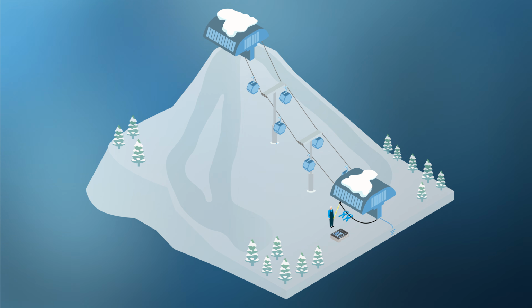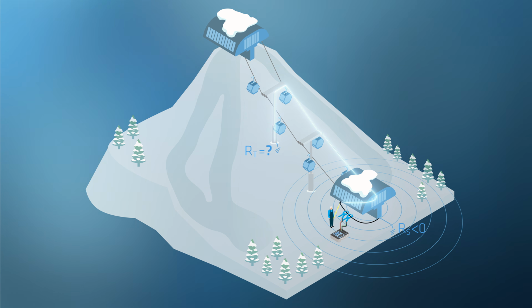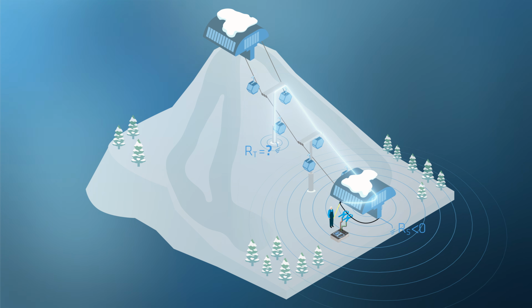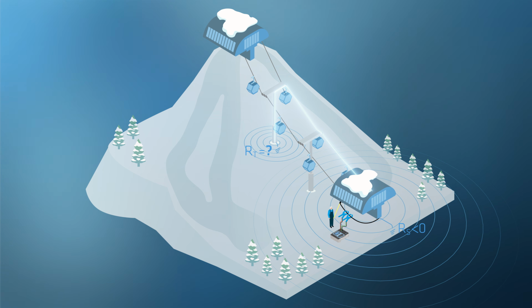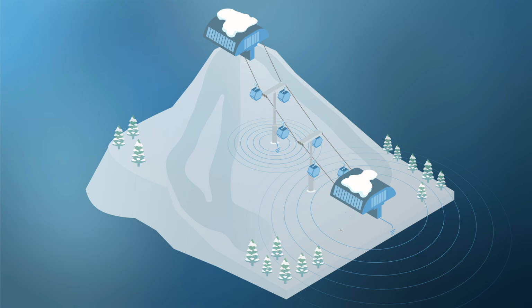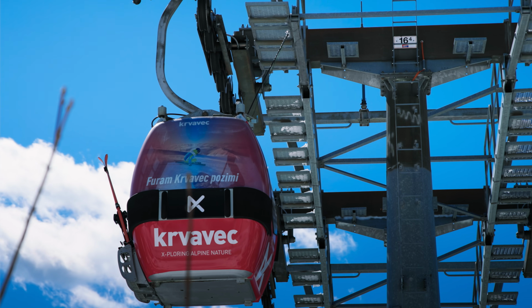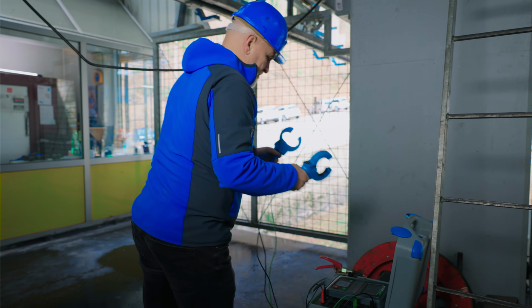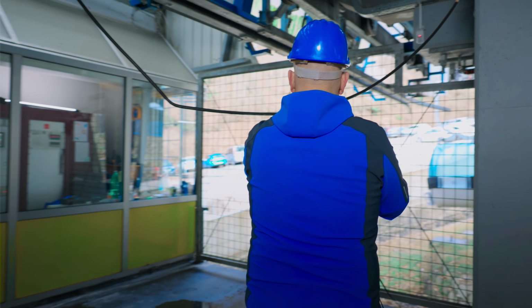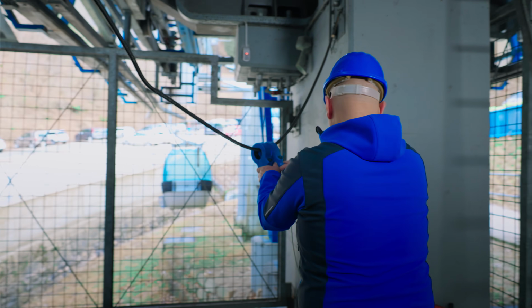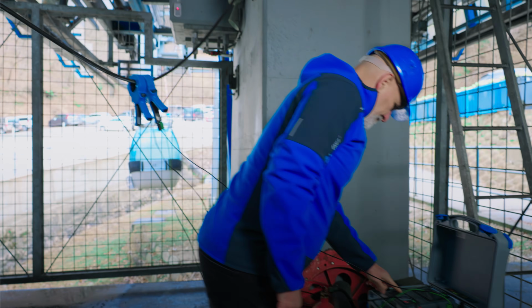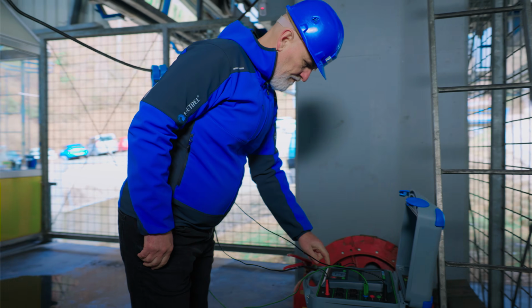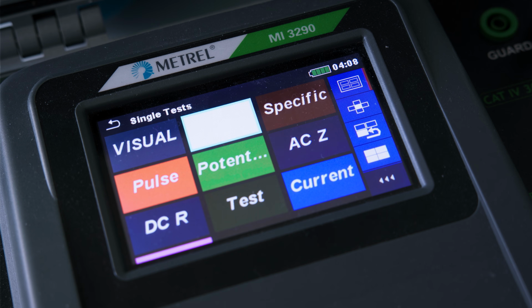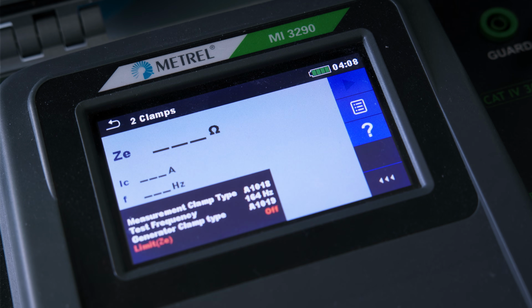Another option is to use the MI3290 tester at the lower station for testing with the grounded carrying cable. In that case, remote assistance at the local tower can be provided by any maintenance team member, eliminating the need to operate the tester. Only a local connection is required between the gondola and the tower's conductive structure. We also use the 2-clamp measuring method with the MI3290 tester. Its memory structure allows easy navigation and later reporting.